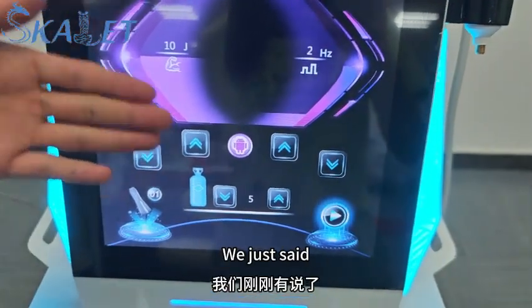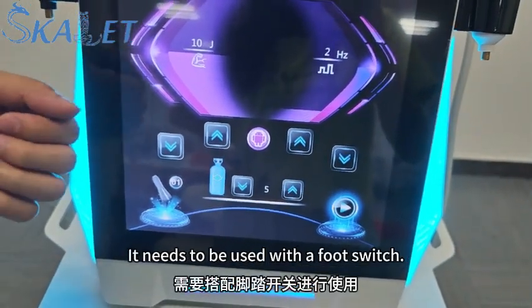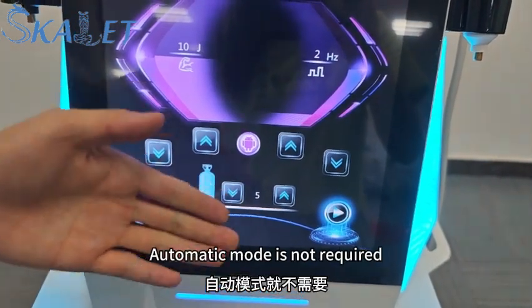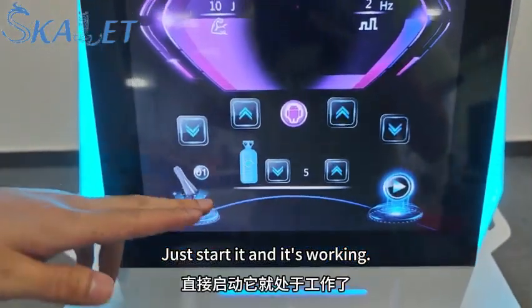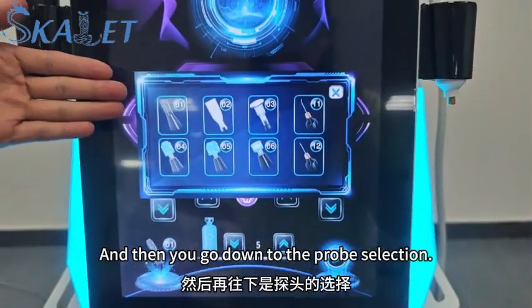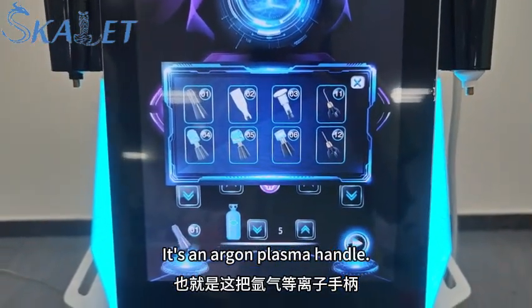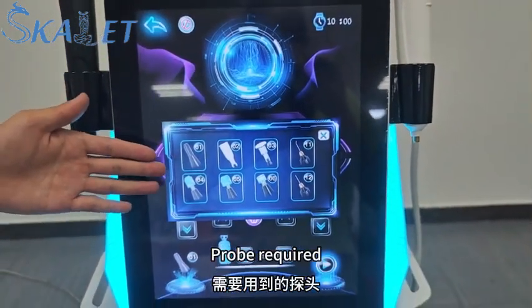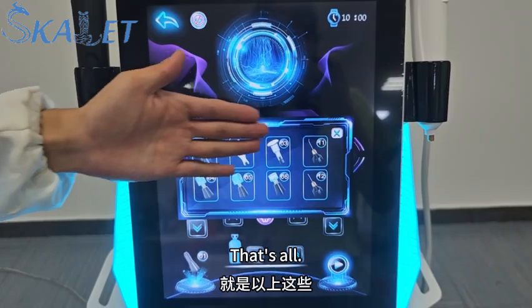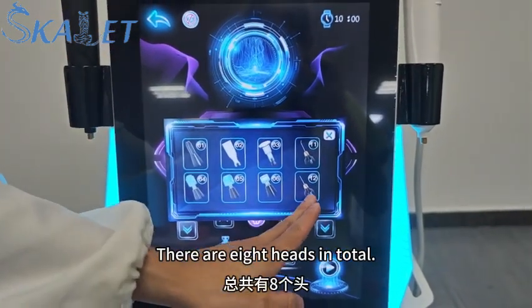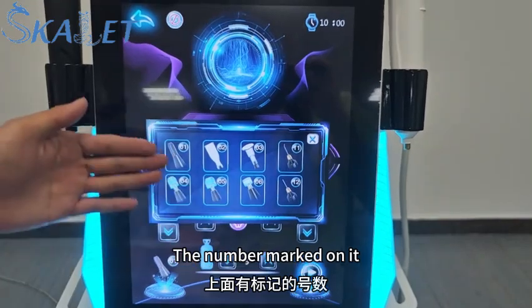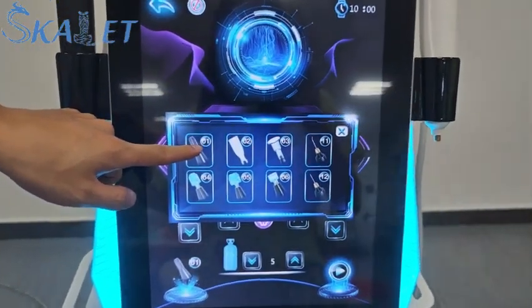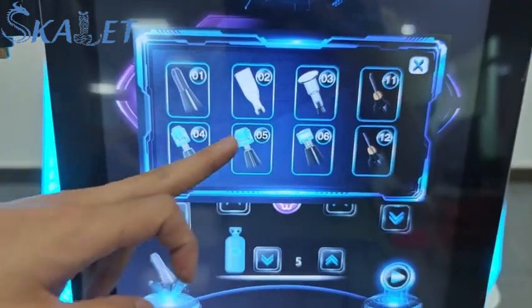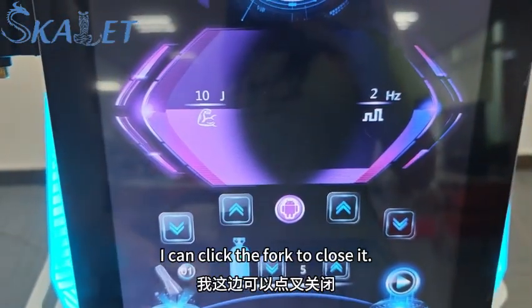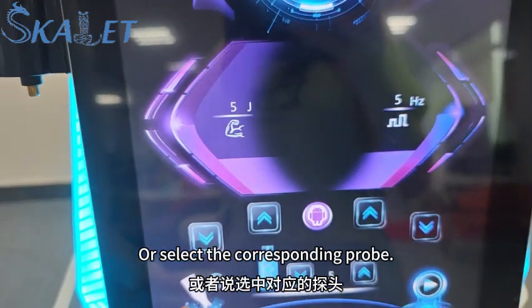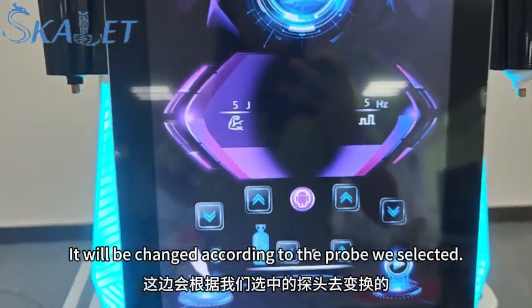We just said manual needs to be used with the foot switch. Automatic mode is not required. Just start it and it's working. And then you go down to the probe selection. It's an argon plasma handle. Probe required, and the probes it can use, that's all. There are 8 heads in total, with the number marked on it. I can click the fork to close it, or select the corresponding probe. It will be changed according to the probe we selected.